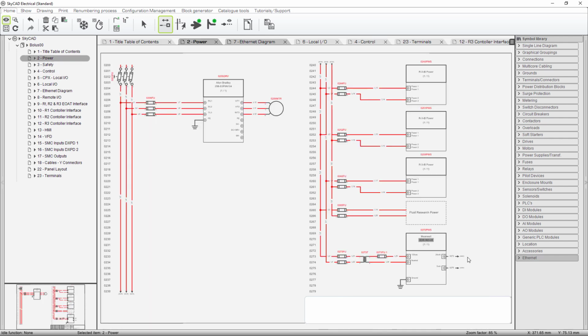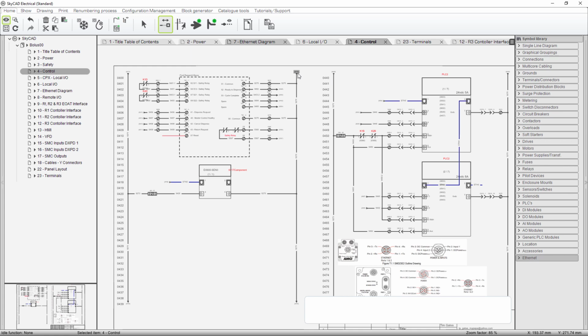And the other wire right here, it's referencing this line number right here, which is really the same line number, 0400. Okay, so this is 24 volts DC and that's 0 volts DC. This reference down here from this arrow is linked to that wire, and this one is linked to that wire. And then down at the bottom here, this one is linked to the top wire on the left corner in the next sheet, and so forth and so forth. You'll see that all the way through the drawing set.